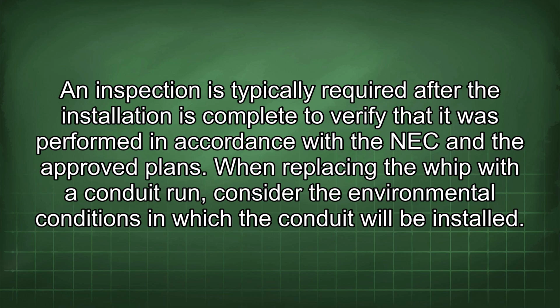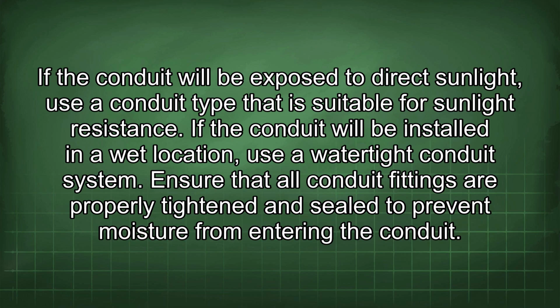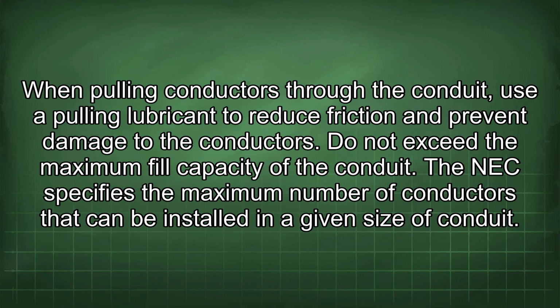When replacing the whip with a conduit run, consider the environmental conditions in which the conduit will be installed. If the conduit will be exposed to direct sunlight, use a conduit type that is suitable for sunlight resistance. If the conduit will be installed in a wet location, use a watertight conduit system. Ensure that all conduit fittings are properly tightened and sealed to prevent moisture from entering the conduit. When pulling conductors through the conduit, use a pulling lubricant to reduce friction and prevent damage to the conductors. Do not exceed the maximum fill capacity of the conduit.